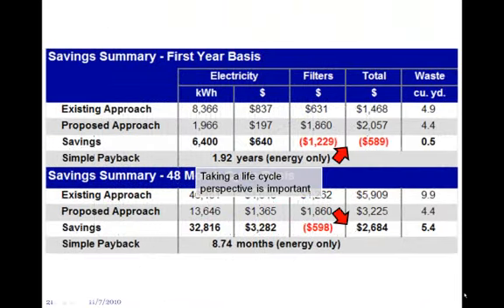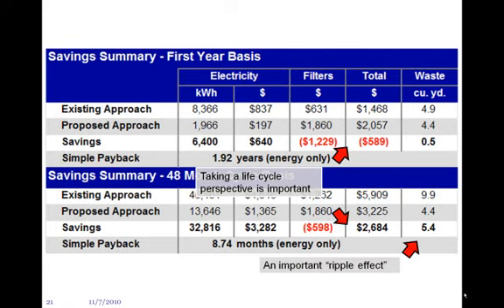Here are basically the numbers on that chart. One of the key points is it's really important to take a life cycle perspective. They were running filters two years anyway. Looking at just one year, which programs tend to do, it saves energy but there's a net cost loss. But at the end of four years, there's a significant benefit both in energy, even though there is a slight penalty still on first cost for the filters.